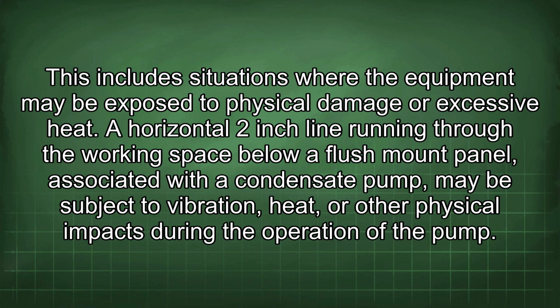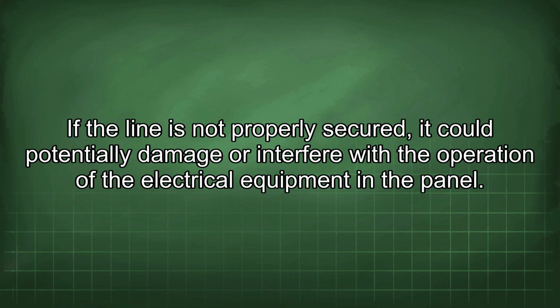A horizontal 2-inch line running through the working space below a flush mount panel associated with a condensate pump may be subject to vibration, heat, or other physical impacts during the operation of the pump. If the line is not properly secured, it could potentially damage or interfere with the operation of the electrical equipment in the panel.